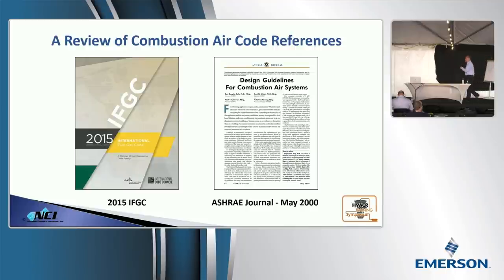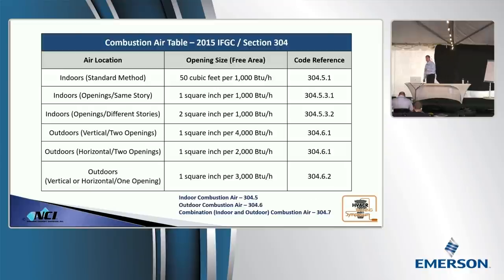Now, as far as code goes, there are numbers. We have to consider where the air for combustion is coming from. Where should combustion air go? If you've got fuel-fired equipment, let's say a standard water heater and furnace installation, where does the combustion air need to go? What needs the combustion air? I know this sounds super simple. The flame, the burner. The burner needs oxygen. It doesn't need the nitrogen. The nitrogen is actually useless in the combustion process. It needs oxygen. The assumption being made here is that if we do this, the equipment is going to get the oxygen that it needs.